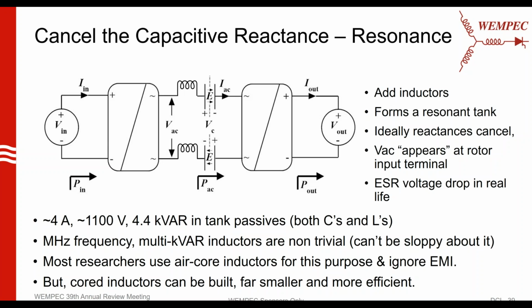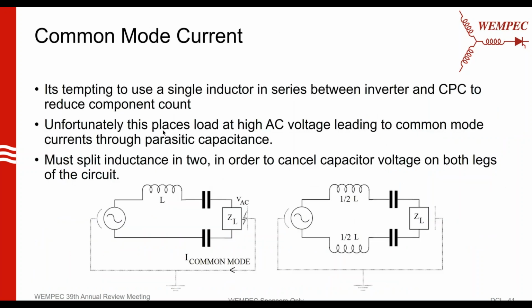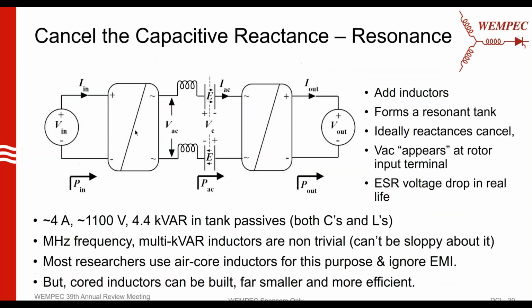Correct. So what does it mean if I do this design with 1 ampere instead? It would mean either a lower transfer efficiency or a bigger size for the system. If you transfer at 1 ampere instead of 3, you could either have a higher DC bus on your GAN inverter and use more voltage at a lower current on the AC side, or, unless you increase the voltage, you won't be able to transfer as much power.